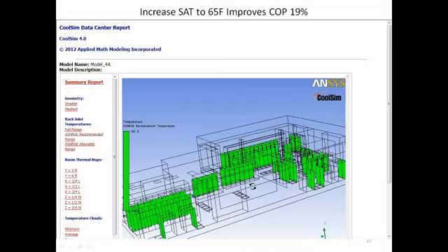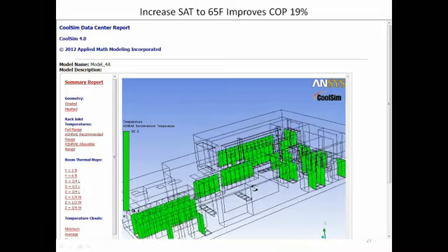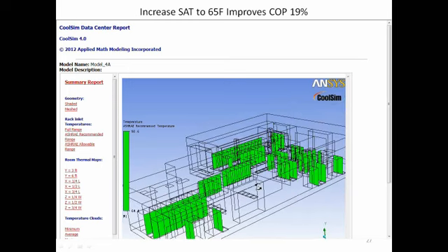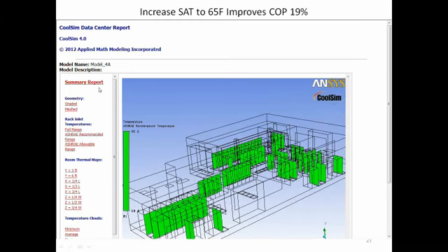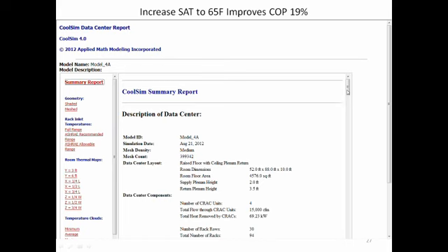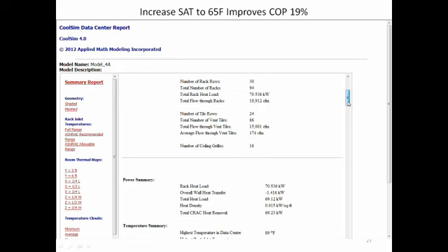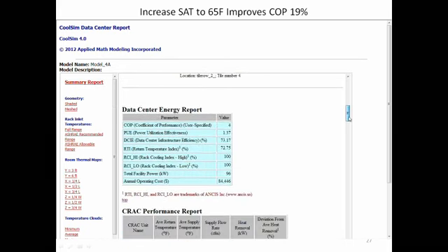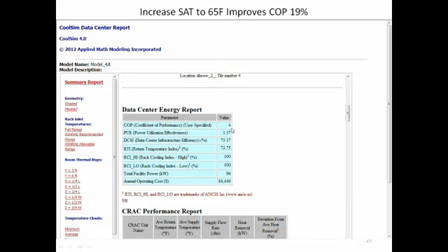So we're doing much better. Now we've got the racks in compliance. They're all in compliance. We're operating the set point at 65 degrees of supply air. We've got one CRAC unit on. Now many of you will say, and look at the COP now at 4.